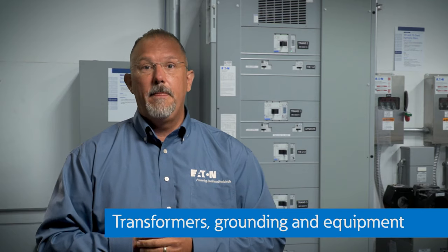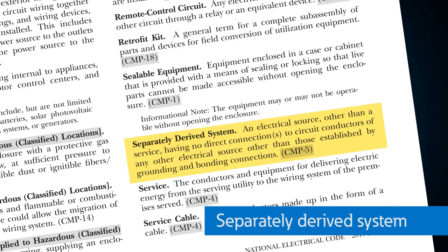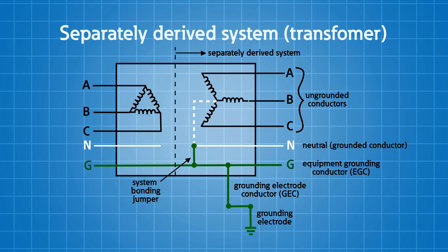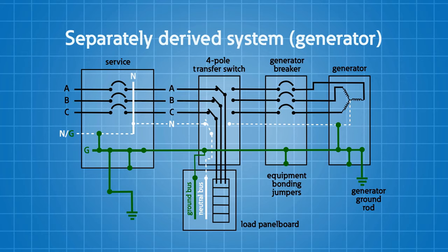Now we're going to move to transformers and grounding and bonding inside transformers — specifically the separately derived system. This is an electrical source, other than a service, having no direct connections to circuit conductors of any other electrical source other than those established by grounding and bonding connections. A common example is a delta-wye grounded transformer in a power distribution system: there is isolation between the primary and the secondary, establishing a separately derived system on the secondary. With a generator, you'll typically see people drive a ground rod next to it and bond the enclosure to that ground rod — if they also connect the neutral to that enclosure inside the generator, they're establishing a separately derived system.